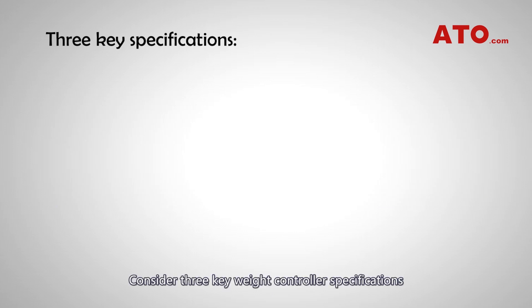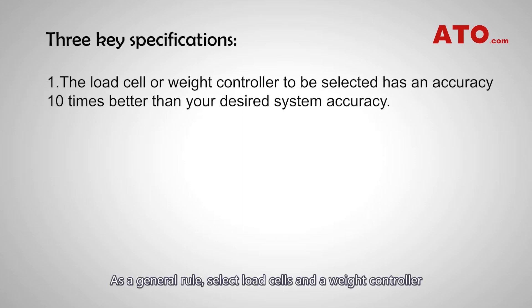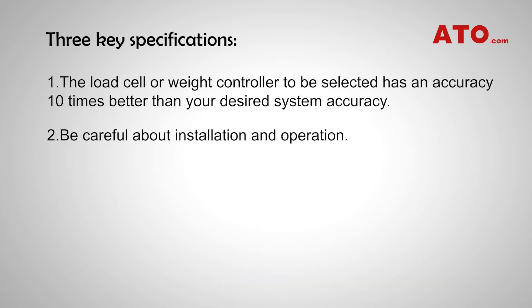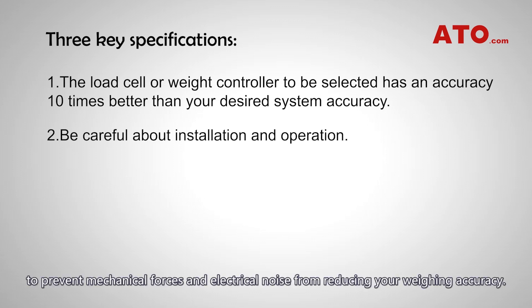Consider three key weight controller specifications to ensure that your weighing system is accurate. As a general rule, select load cells and a weight controller with accuracies 10 times better than your desired system accuracy. And pay close attention to how you install and operate the system to prevent mechanical forces and electrical noise from reducing your weighing accuracy.